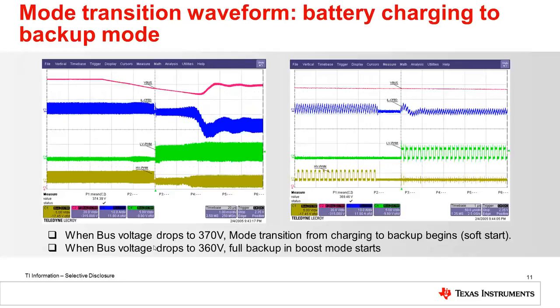This slide shows the mode transition waveform when the system moves from the battery charging mode to the backup mode. Initially, when the DC bus voltage stays above 380 volts, the system stays in the battery charging mode. And when the DC bus falls to around 370 volts, the system moves from battery charging mode to the backup mode. The time taken to move from the battery charging to the backup mode is less than 100 microseconds and is typically around 80 microseconds in most cases.